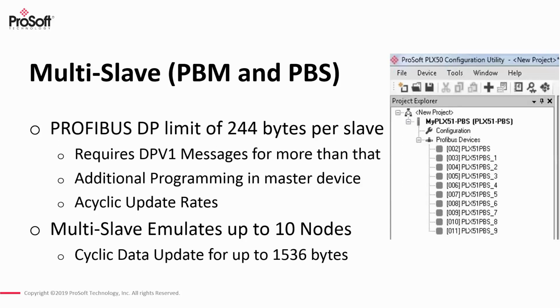This required additional programming in the master device, and again, since it was acyclic data, the update rate wasn't necessarily deterministic. It was just based on the bus and when they could get additional information out there. So with the multi-slave mode, we are able to emulate up to 10 independent nodes on the network. So there's still a single connection on the module. So as you're wiring the network out there, you're still wiring an individual Profibus connection to either the PBM or the PBS module. But in software, that module can emulate up to 10 unique node IDs on the Profibus network.